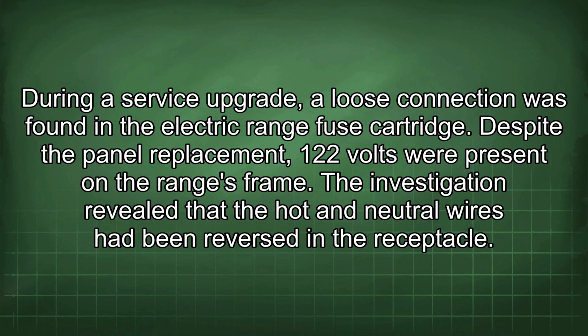During a service upgrade, a loose connection was found in the electric range fuse cartridge. Despite the panel replacement, 122 volts were present on the range's frame. The investigation revealed that the hot and neutral wires had been reversed in the receptacle.